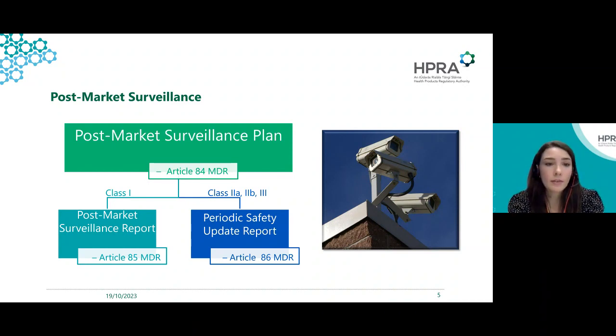The manufacturers then of Class 1 devices shall prepare a post-market surveillance report. This summarises the results and conclusions of the post-market surveillance data gathered as a result of the post-market surveillance plan, together with rationale and description of any preventive and corrective actions taken. The report is updated as needed and made available to the competent authority upon request.